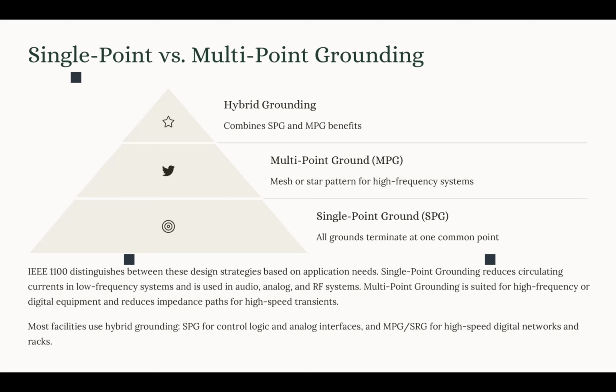Now, we design those topologies to provide a stable low noise reference plane, so we could make sure that our sensitive equipment works properly. And there is the safety aspect and the EMC requirement in those designs. Now, in the single point grounding, all the grounds terminate at a single point. So it's like a star connection. So there is only one bonding point between the equipment chassis and the building ground system.